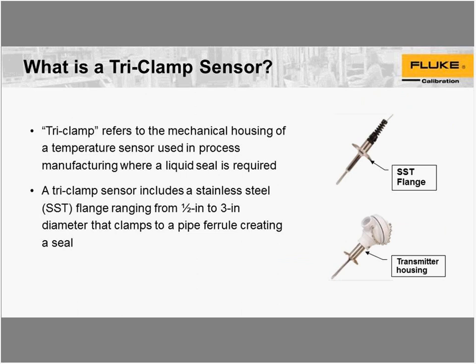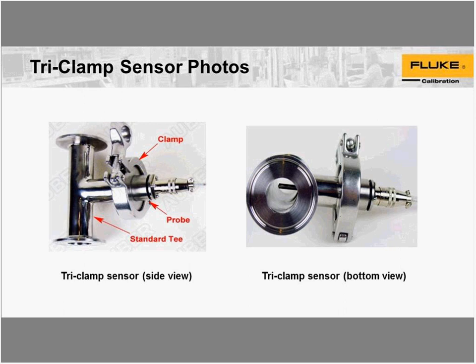A tri-clamp sensor is a sensor that has this flange, and what this flange does is allow the sensor to be easily clamped into a pipe or some kind of manifold system. In this case, temperature sensors can measure the temperature in the manufacturing process. Here is a closer look at what the setup looks like. We are very familiar with this, but we thought it would be good to review in case there's someone who isn't familiar with tri-clamp. So basically, this is the sensor, and it shows how a clamp ring goes around the flange and allows someone to easily clamp into a system for a leak-free connection.